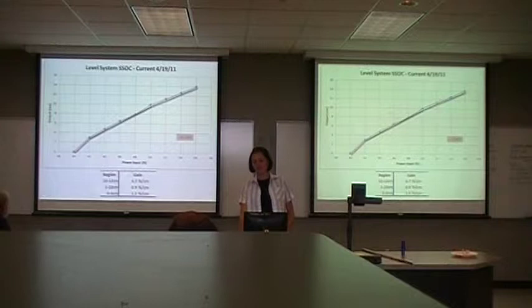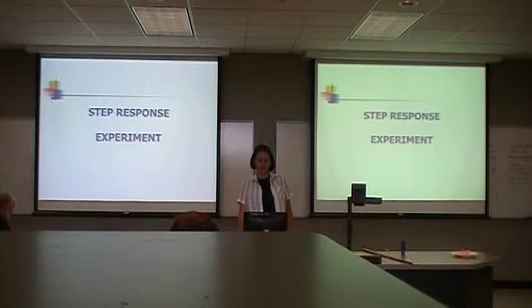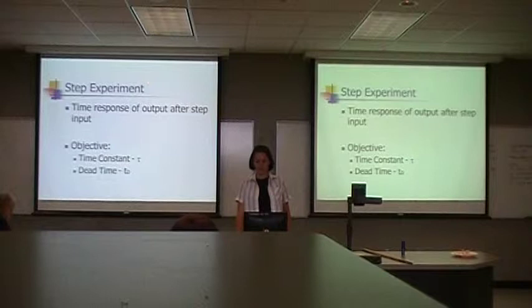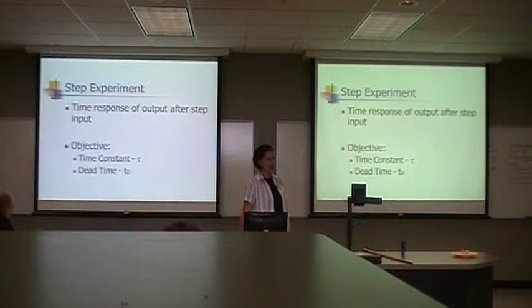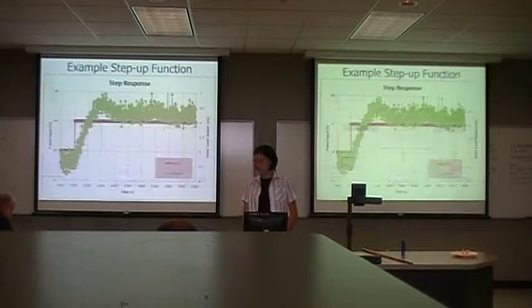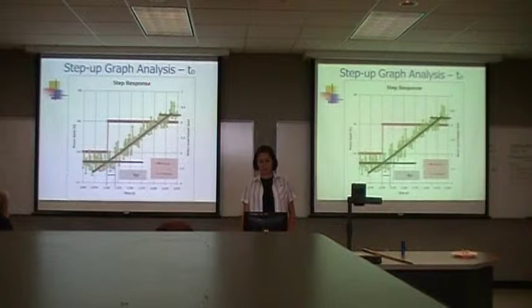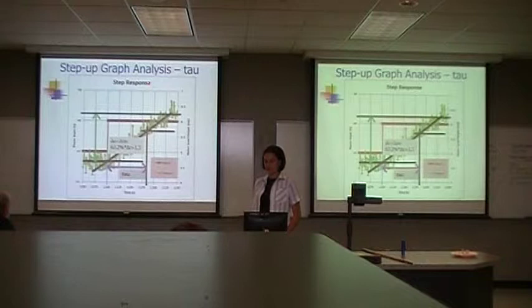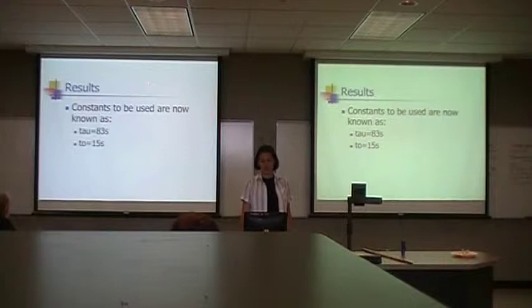This was in the middle of April, so happy day. While I was making the new SSOC, I also did a step response. Step response helps you find tau and t-naught, which you use when you're calculating the PI model. There's t-naught — the time it takes to start responding — and tau is delta C times 63.2%. We use those equations, and these are the constants for our system.